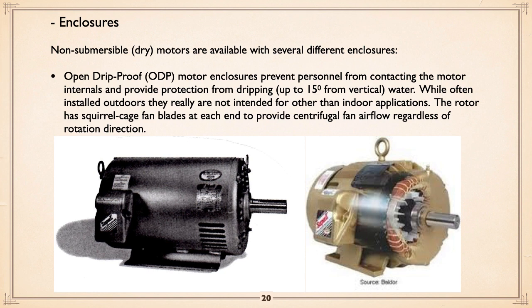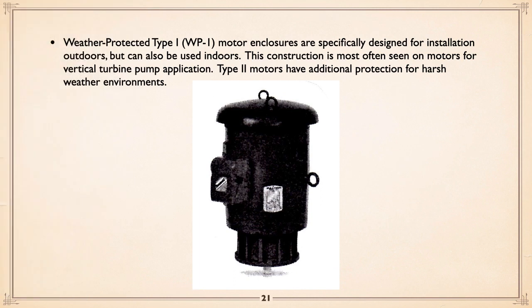And we need cooling air for these things. It helps a lot. So we have a centrifugal fan at each end of the motor, so air will come in from the ends and blow out the side. You see the side louvers on the thing. And as the motor spins, so does the fan. Now, upgrading that, we get into weather-protected Type 1, specifically designed for installation outdoors.